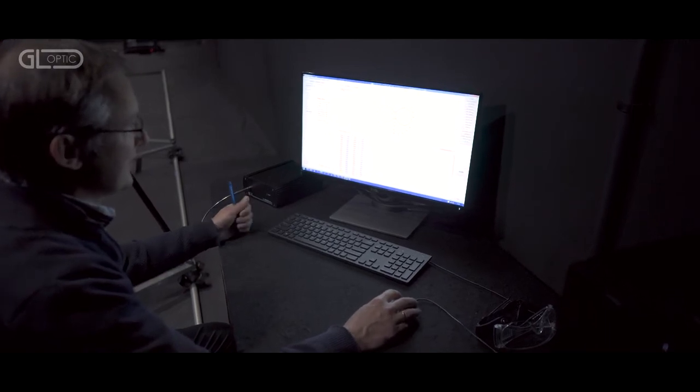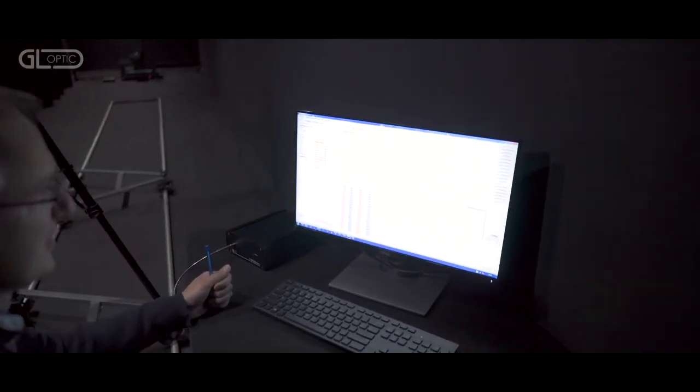So the distance is set. We have to make sure that the measurement type is radiometric measurements. The range that we want to register for the spectroradiometric measurements is also set. In this case, we put it at 245 to 265 nanometers, which will make sure that we cover the mercury emission line.